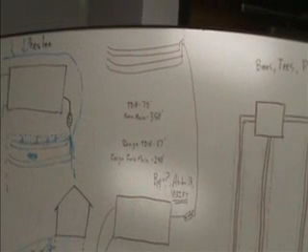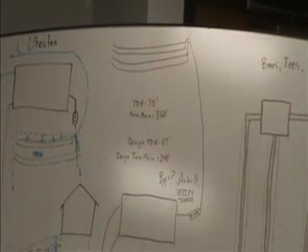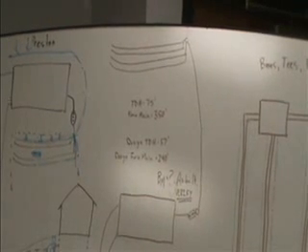It was huge. This hill was enormous. So that, from the very beginning, is a difficult system to determine your head on. So you've got to be very careful. So the first message is be very careful when you're trying to determine your head on a system like that.